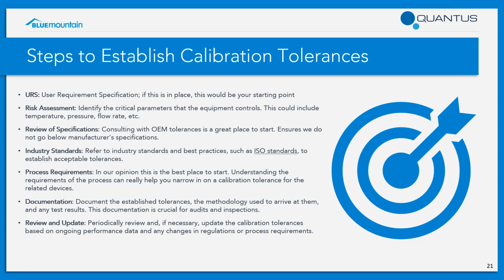If you know the process, the safe bet is going to be having that process tolerance as your calibration tolerance. That way, if you're outside of that, you're not directly impacting your manufacturing operations. So whatever you decide, from a documentation standpoint, we're going to suggest that customers document that decision on calibration and process tolerances within your CMMS or on an equipment master record. It is going to be the responsibility of the customer to maintain this information, and auditors do routinely ask where this information came from. And then finally, review and update.